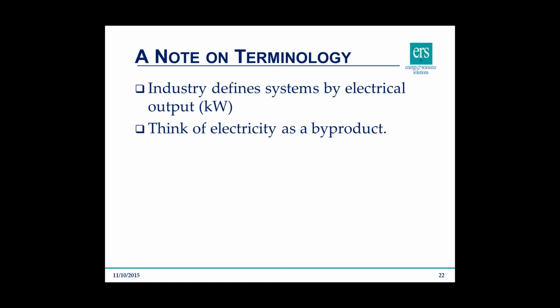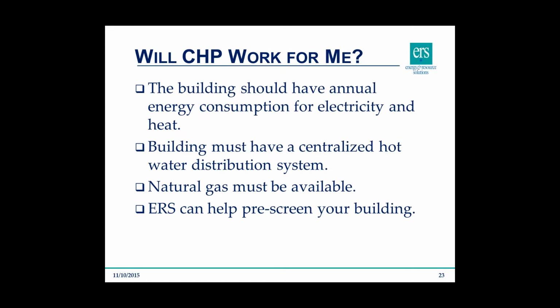So, will CHP be a good fit for your facility? The answer is yes, if your building has a significant annual need for both electricity and thermal needs, then CHP might be a good solution. The building should have some centralized way to get the thermal load to end uses. Typically we see that as a centralized domestic hot water system or a space heating system. All of the systems that are incented by NYSERDA's CHP acceleration program do run on natural gas. So natural gas must be available at your facility, and in sufficient quantity to run the CHP system.